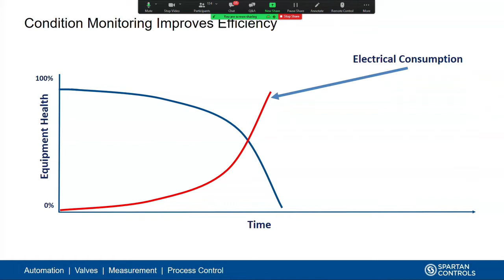As that pump starts to degrade, as its efficiency starts to decline, the VFD needs to compensate by increasing the speed of that pump and therefore using more electricity. We've got a lot of these applications, particularly on large horsepower motors and large pumps, where we're going to be consuming much more energy.